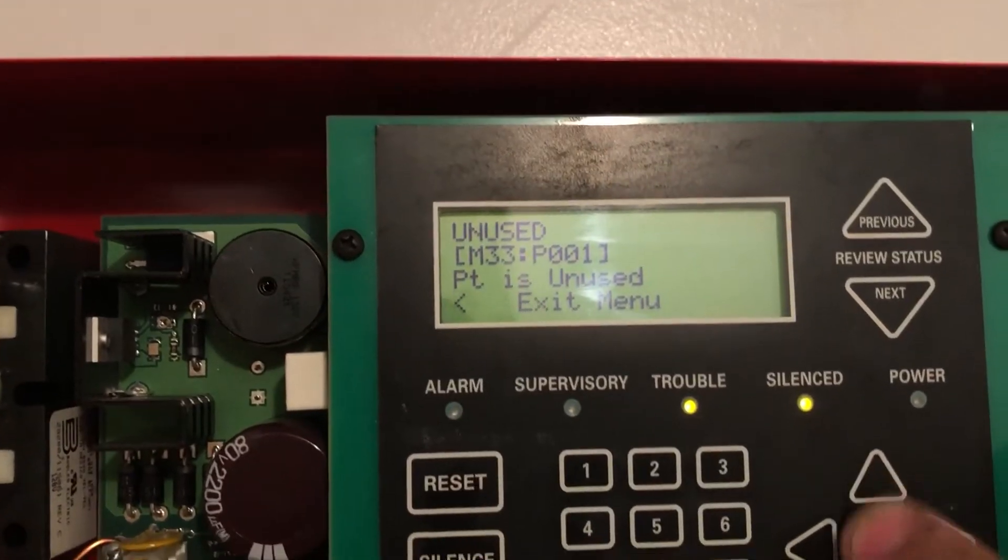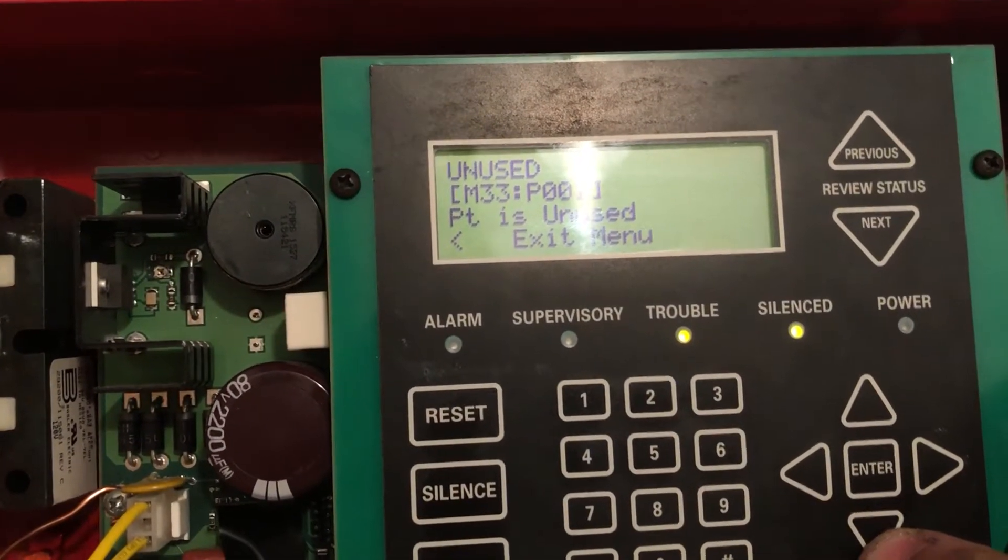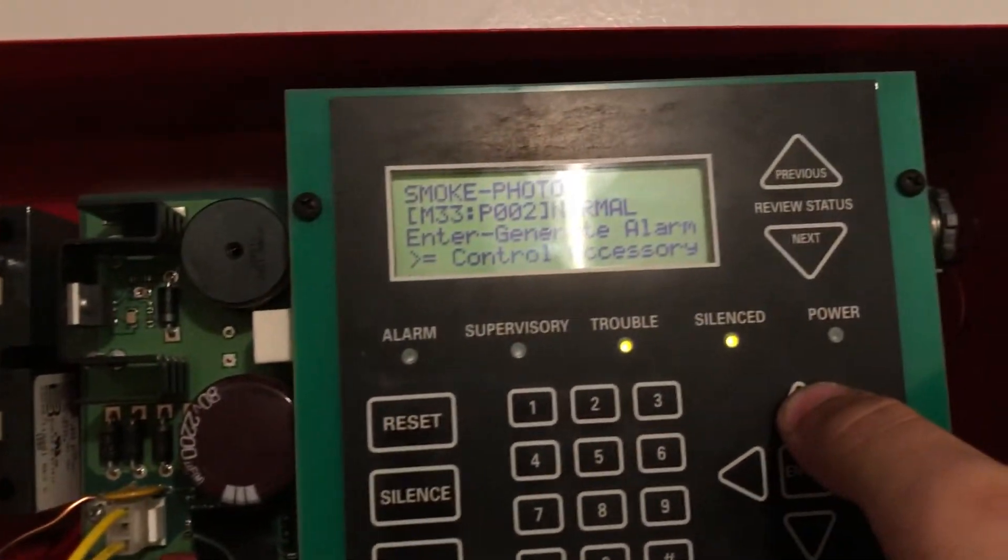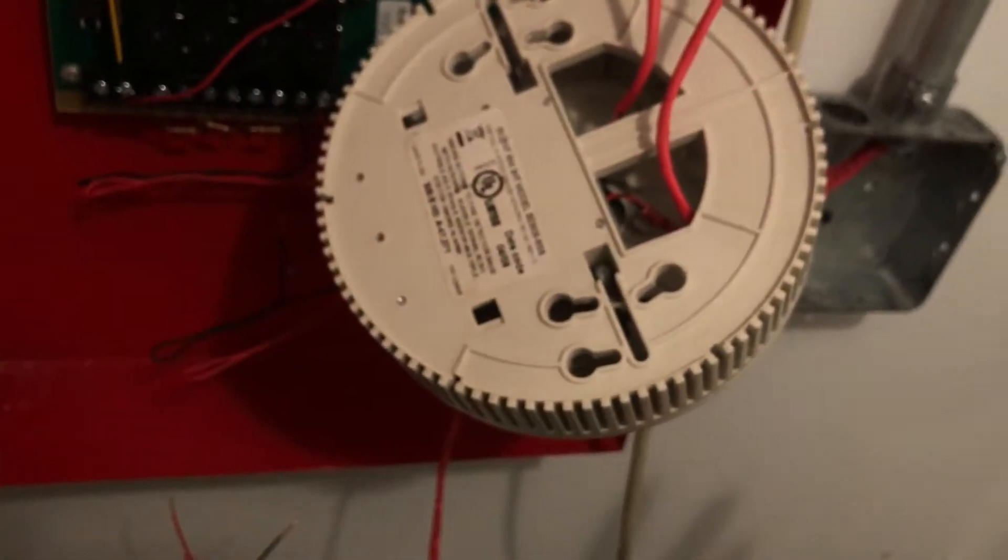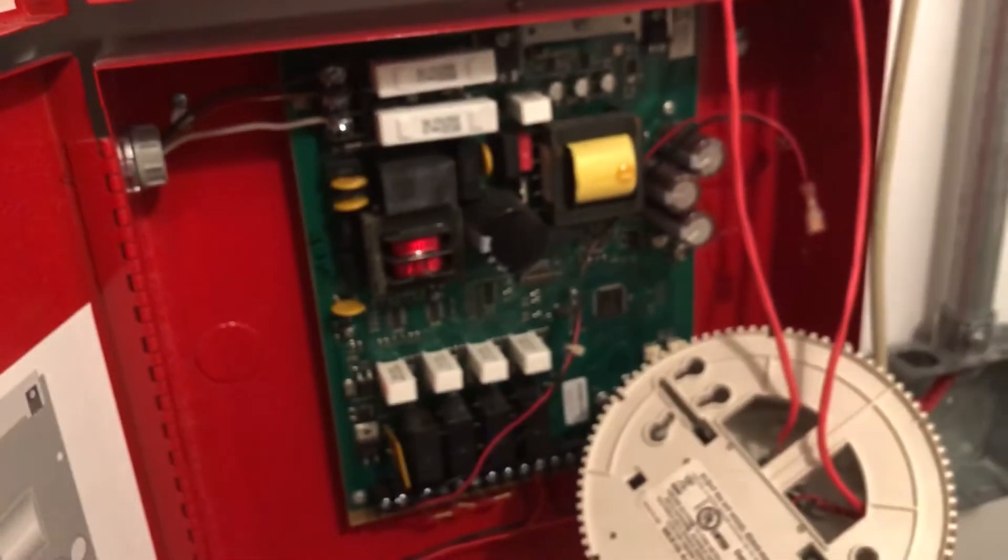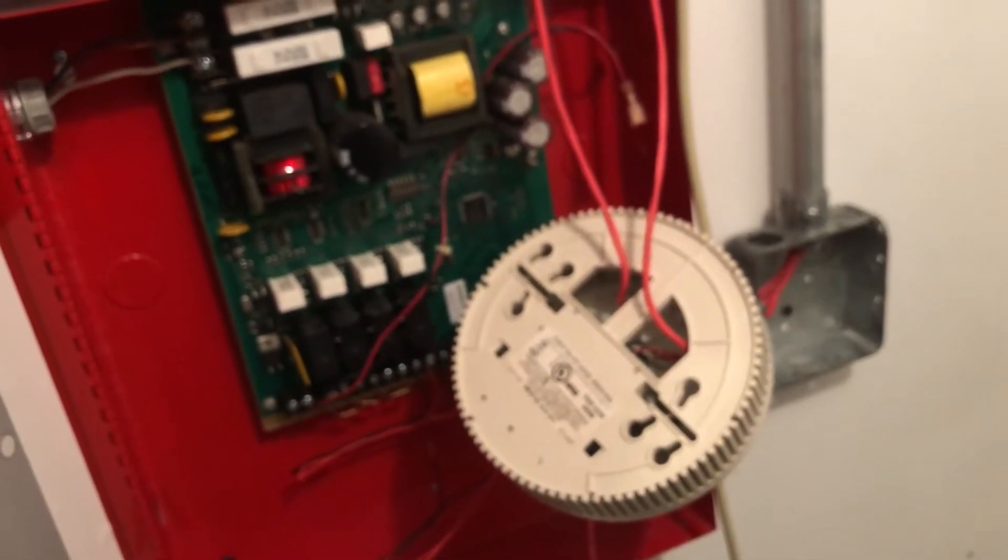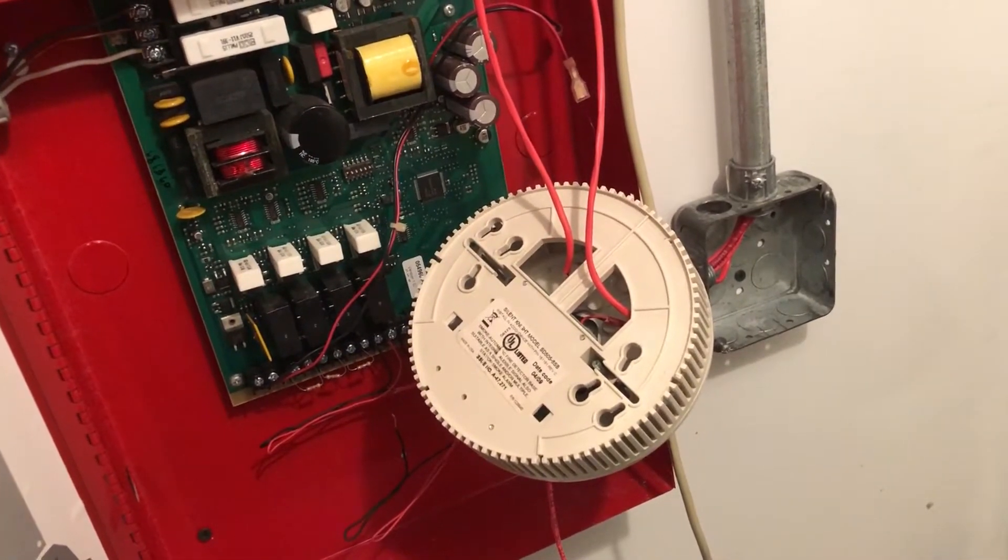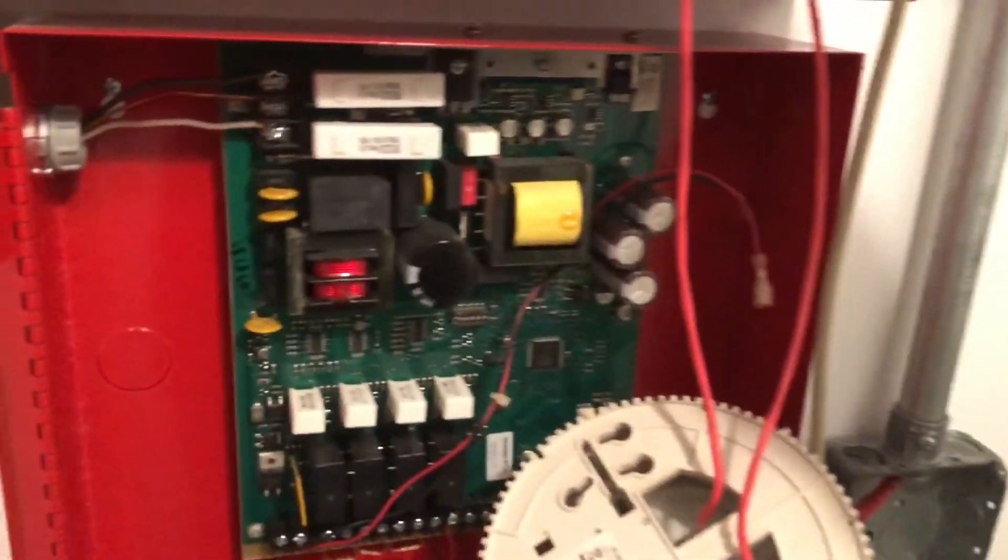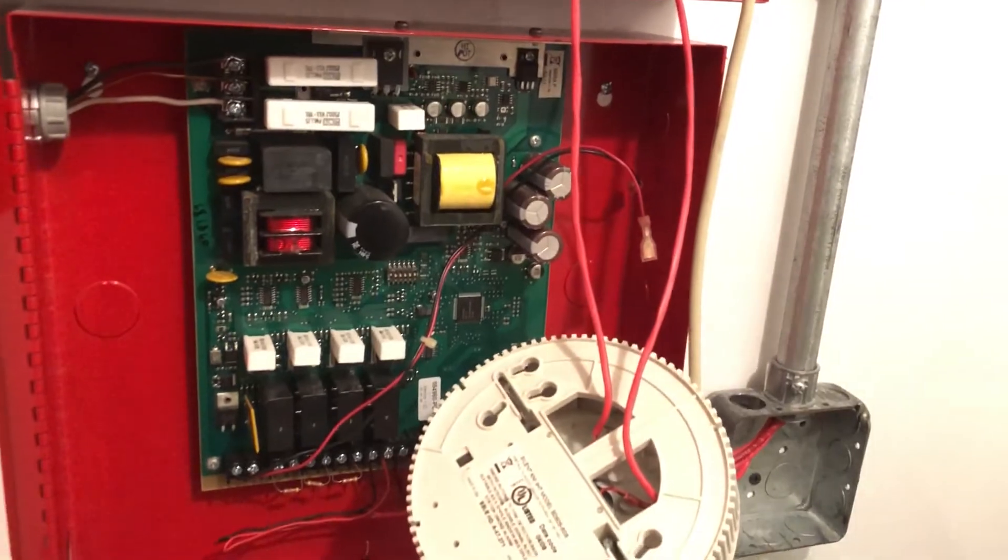So we're going to go down to IO point control, internal SLC. And we're going to try the supervisory first because it's the least priority alarm. So this will beep that kind of crazy one. So let's see if it works. Three, two, one. And there we go.